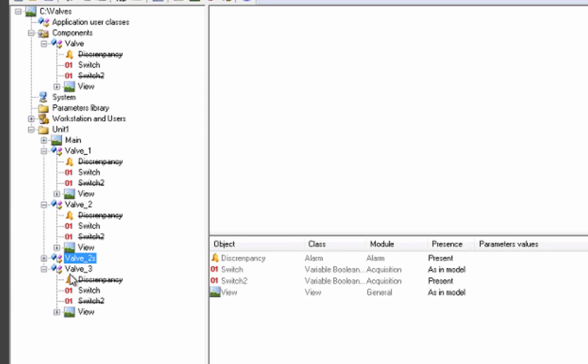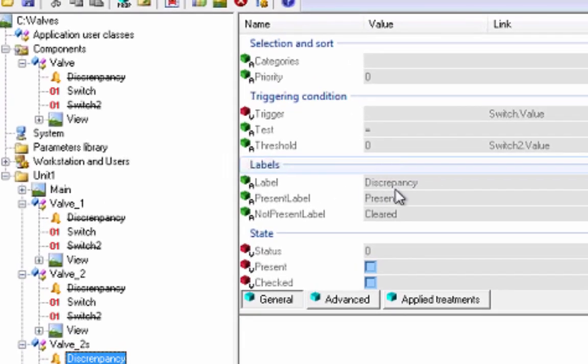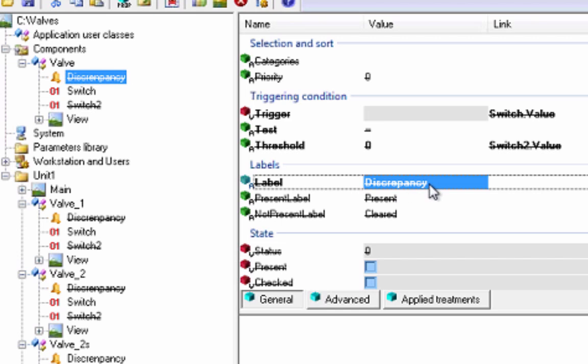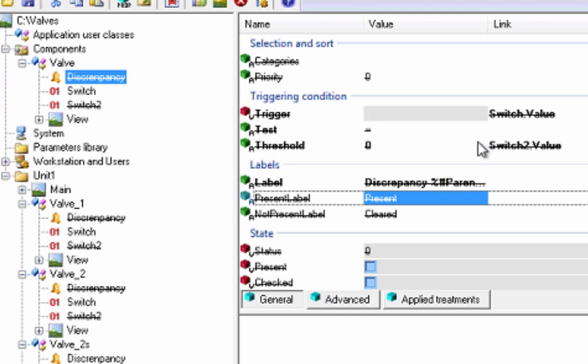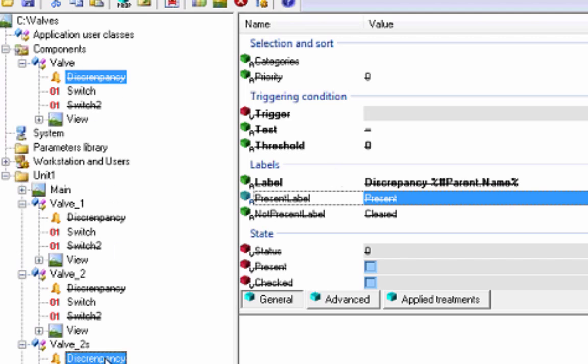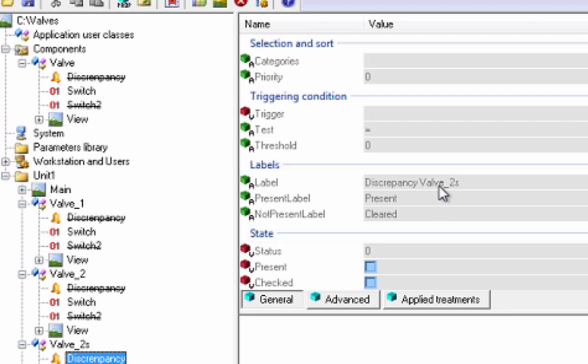Okay, now we have an alarm. The problem is that the alarm has a very simple label, discrepancy. If I had several valves, I wouldn't know which alarm goes with which valve. So I need to customize my alarm label so that the valve name appears in it. There is a syntax in Panorama that we can use. When we use % characters, it tells Panorama that it must evaluate what is between the two % signs. So I will use the syntax parent.name, which tells Panorama that it must replace this string by the name property of the object above my alarm, which means the valve. The result is that the valve name automatically appears in my label.